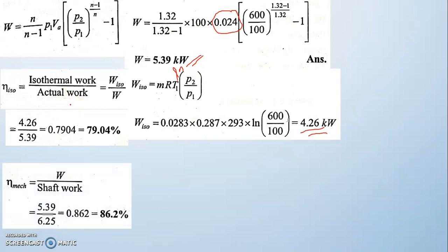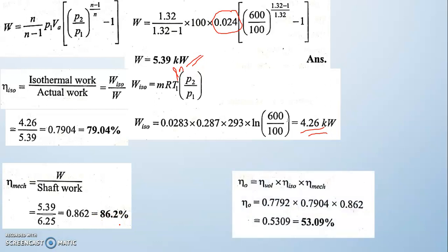Mechanical efficiency is the ratio of indicated (actual compressor) work to shaft work. The compressor is driven by a motor whose power is the shaft power. Not all motor power converts to compression work — some is lost as mechanical friction. Mechanical efficiency = indicated power / shaft power = 86.2%. Overall efficiency is the product of volumetric efficiency × isothermal efficiency × mechanical efficiency = 53.09%.